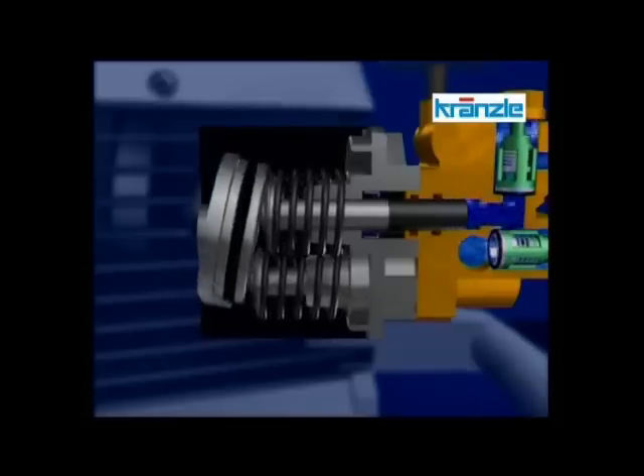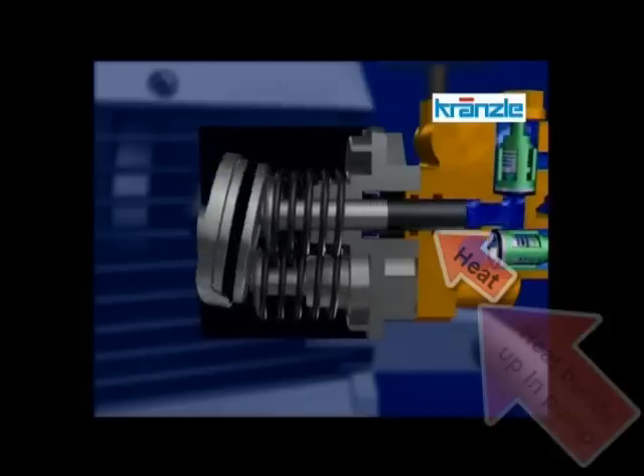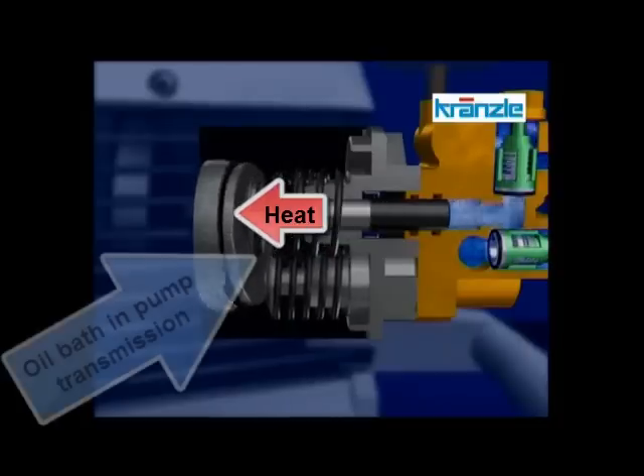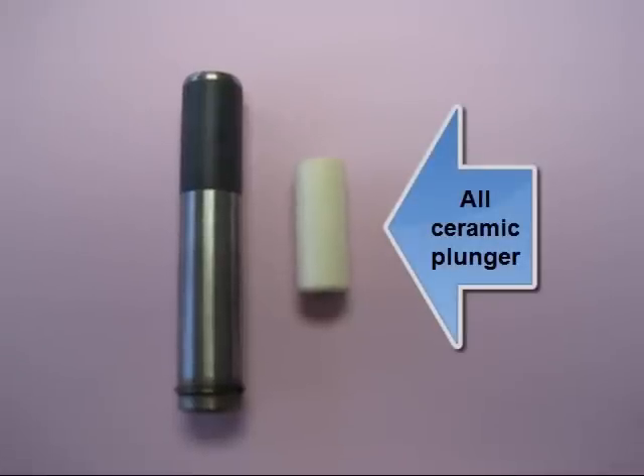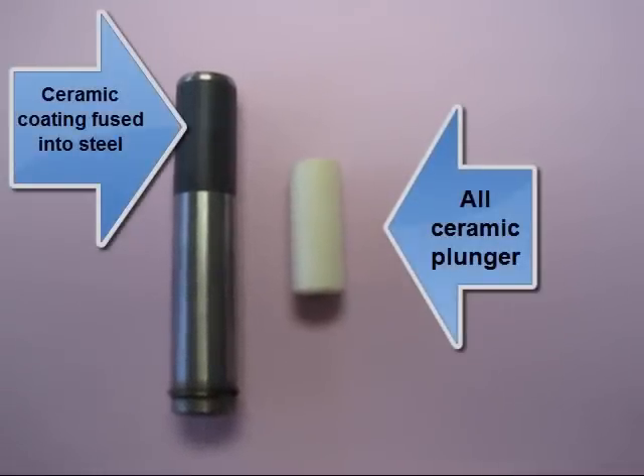Steel is a conductor of heat. The heat that builds up in the pump head of the Kränzle pump passes through the thin ceramic coating on the plunger, down the inside of the steel plunger, to the oil bath in the pump transmission where it is dissipated. Pumps using all-ceramic plungers are incapable of doing this, as ceramic is a poor conductor.